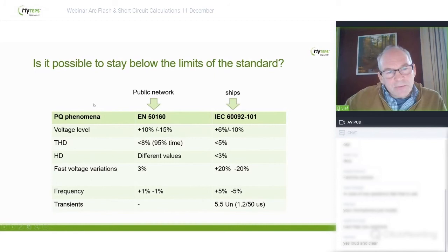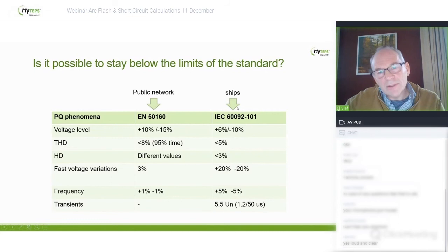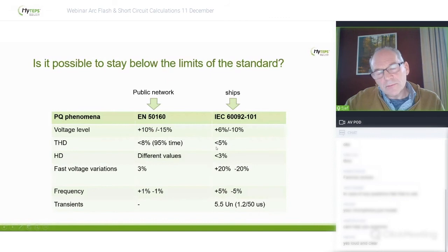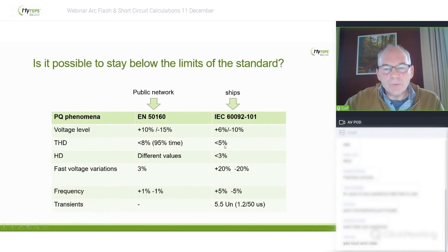The challenge is to design an installation that stays below the limits of the standard. The standard is different for public networks versus ships. For fast voltage variations, the limits are much wider on ships — plus and minus 20 percent compared with public network acceptable variation. But for total harmonic distortion, the limit on a ship is actually stricter than for a public network. And that's the big challenge: this is much more difficult to achieve because the network is weaker. So keeping total harmonic distortion below 5 percent is quite a big challenge.